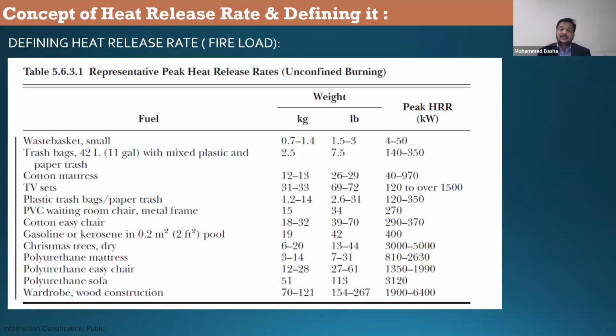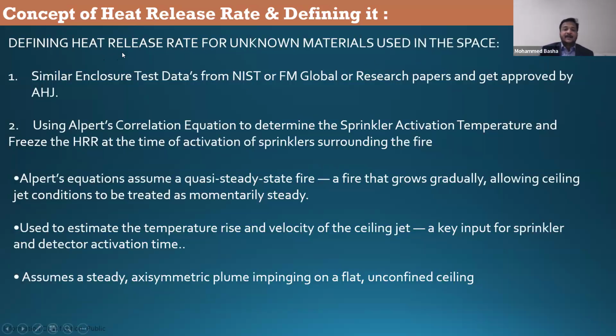So what can we do in this situation? You can see here, defining heat release rate, which is Q, for unknown materials used in the space. Use similar enclosures' test data from NIST, which is called National Institute of Standards and Technology, USA based, or FM Global, which is an insurance company document, or research papers, and get approved by AHJ. For example, you are designing a proscenium stage, a theater kind of a setup. Nowhere is it mentioning what is the HRR for a theater, as we have seen in the tables. Maybe your civil defense will be giving you these values, but our civil defense doesn't have this value. So what can we do? We have to search in NIST or FM Global, because they are third-party agencies where they are doing testing at several laboratories to see what the real Q values required are. You can take from there and submit to the civil defense and get approved in your DC1 stage, I mean the beginning stage.